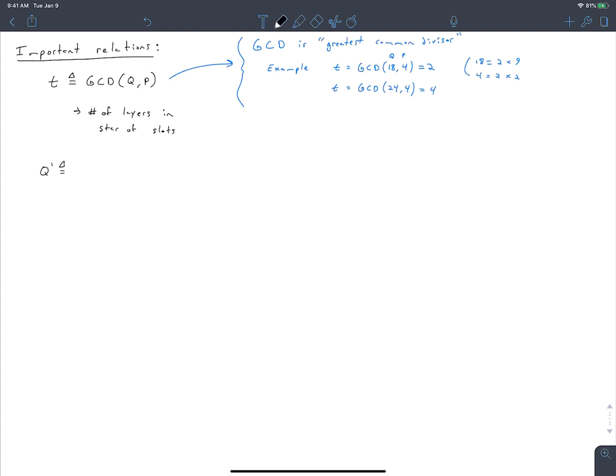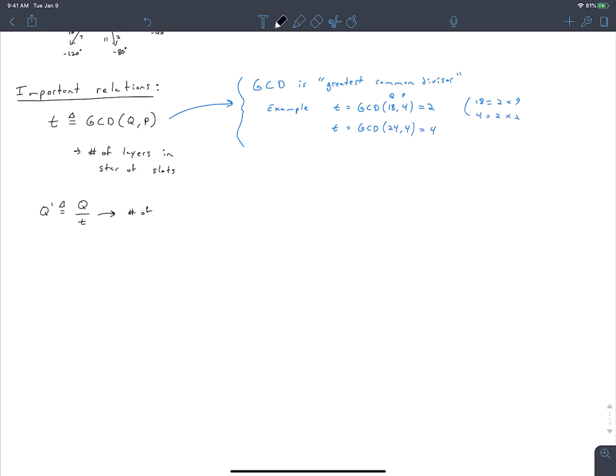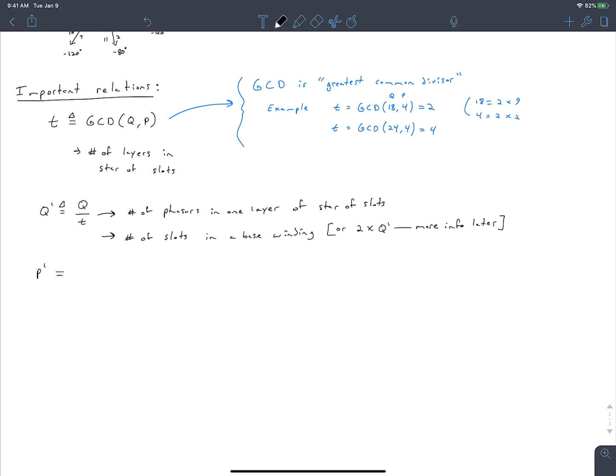Next, we define q prime as the number of slots divided by t. Q prime is the number of phasors in one layer of the star of slots, and also the number of slots in a base winding — though in a later video we'll see that sometimes you need 2 times q prime slots. We also define p prime as p divided by t, which is the number of pole pairs in our base winding, or sometimes 2 times that.